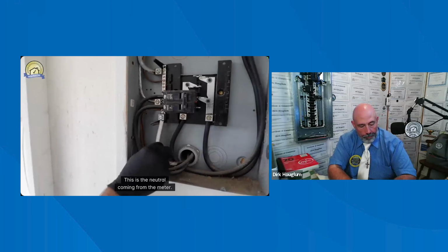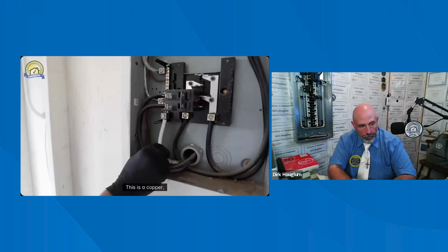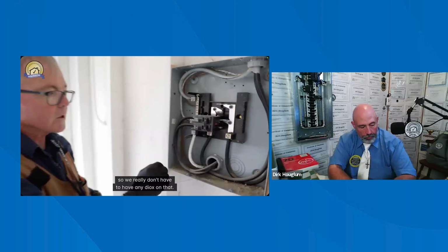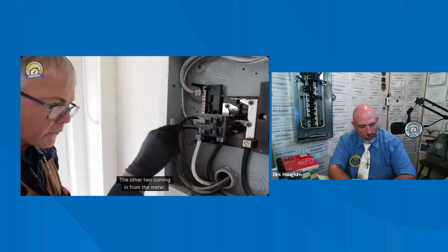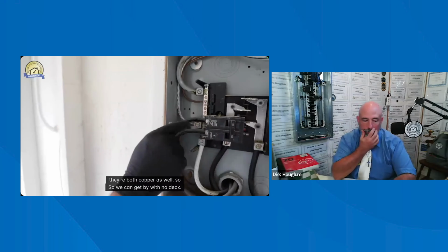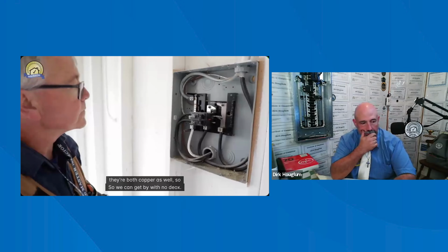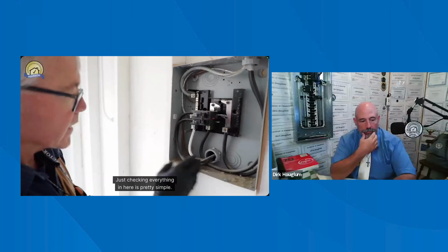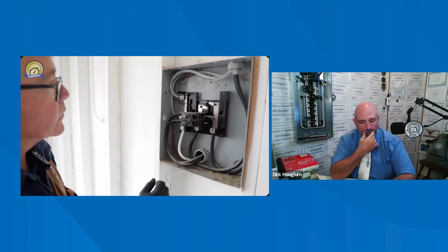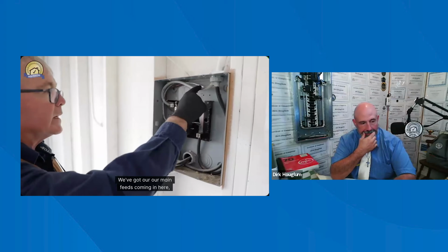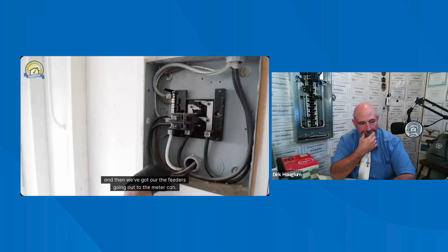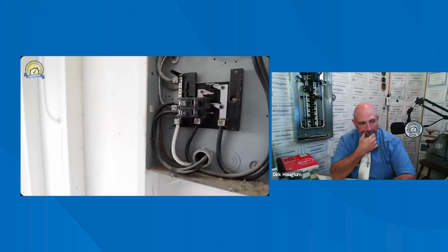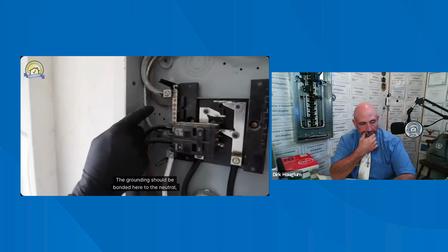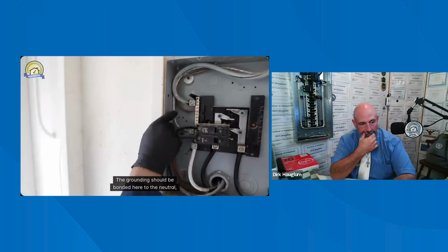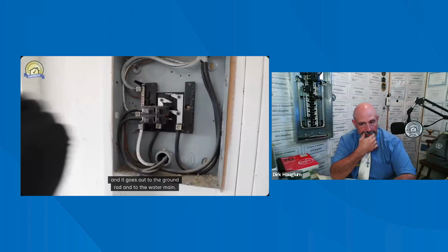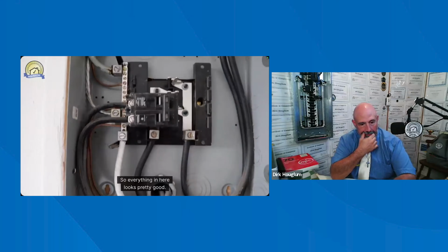This is the neutral coming from the meter. This is copper, so we really don't have to have any deox on that. The other two coming in from the meter are both copper as well, so we can get by with no deox. Just checking everything in here is pretty simple. We've got our main feeds coming in here, and then we've got the feeders going out to the meter can. The grounding is correct. The grounding should be bonded here to the neutral, and it goes out to the ground rod and to the water main. So everything in here looks pretty good.